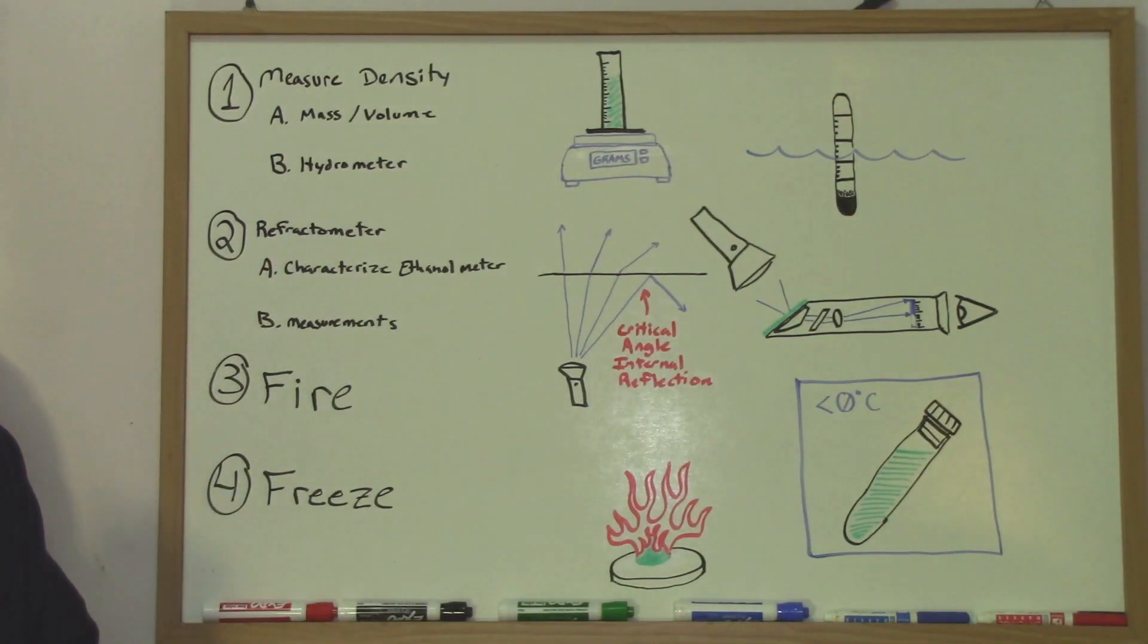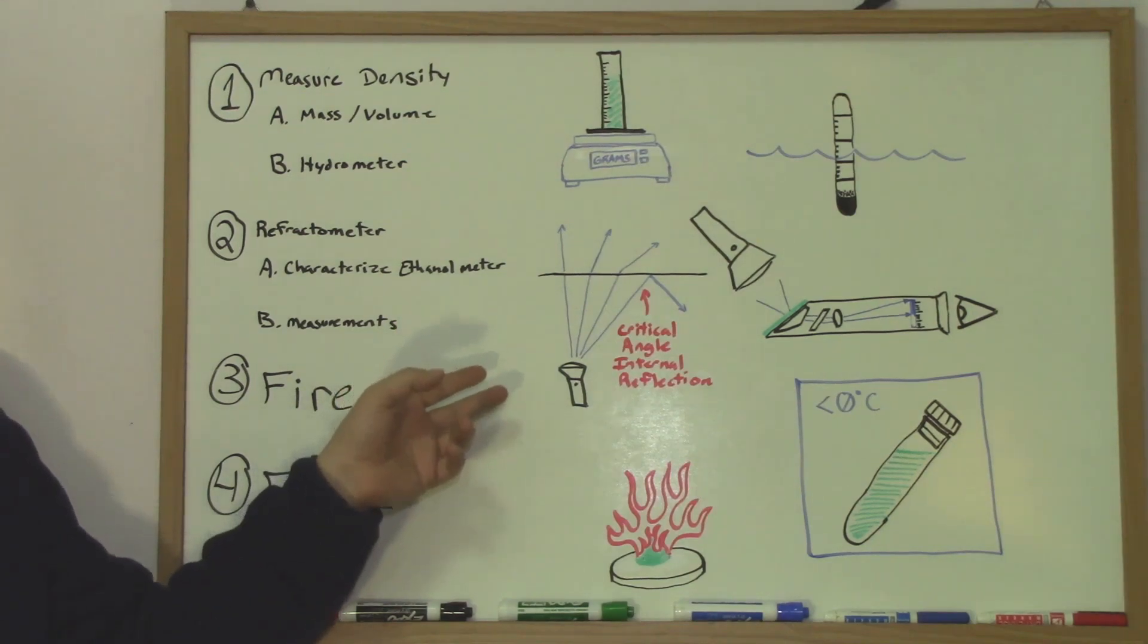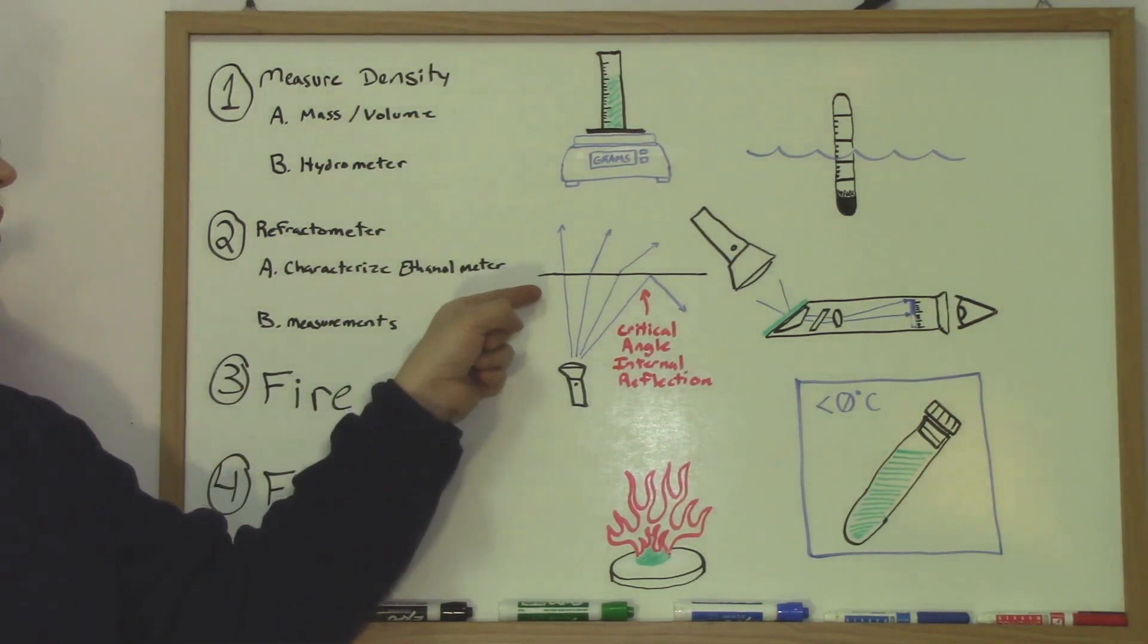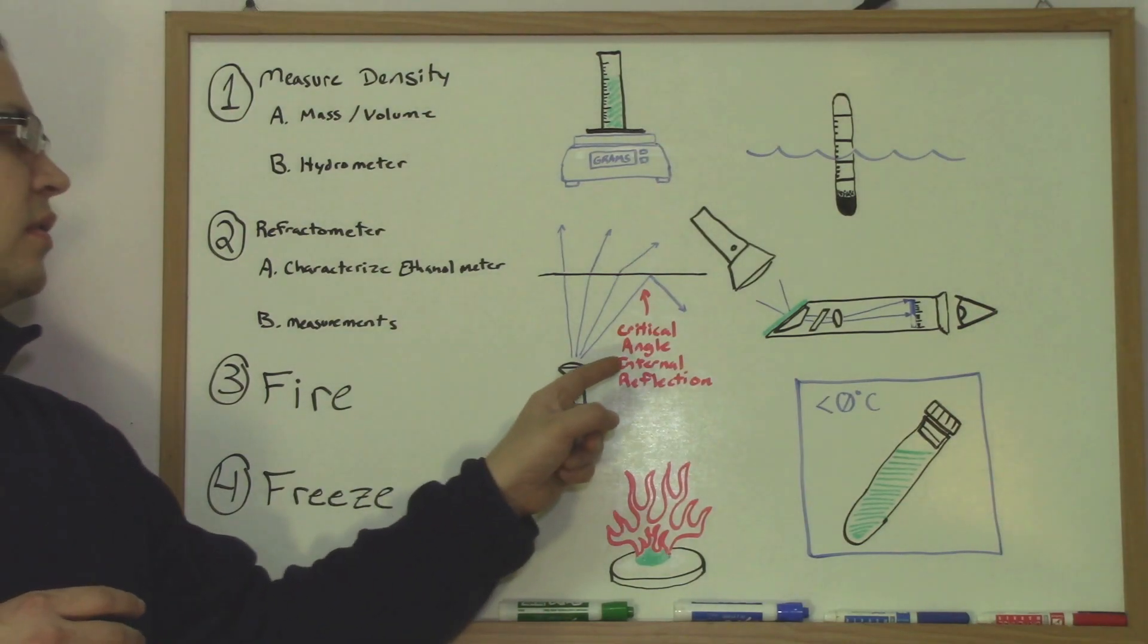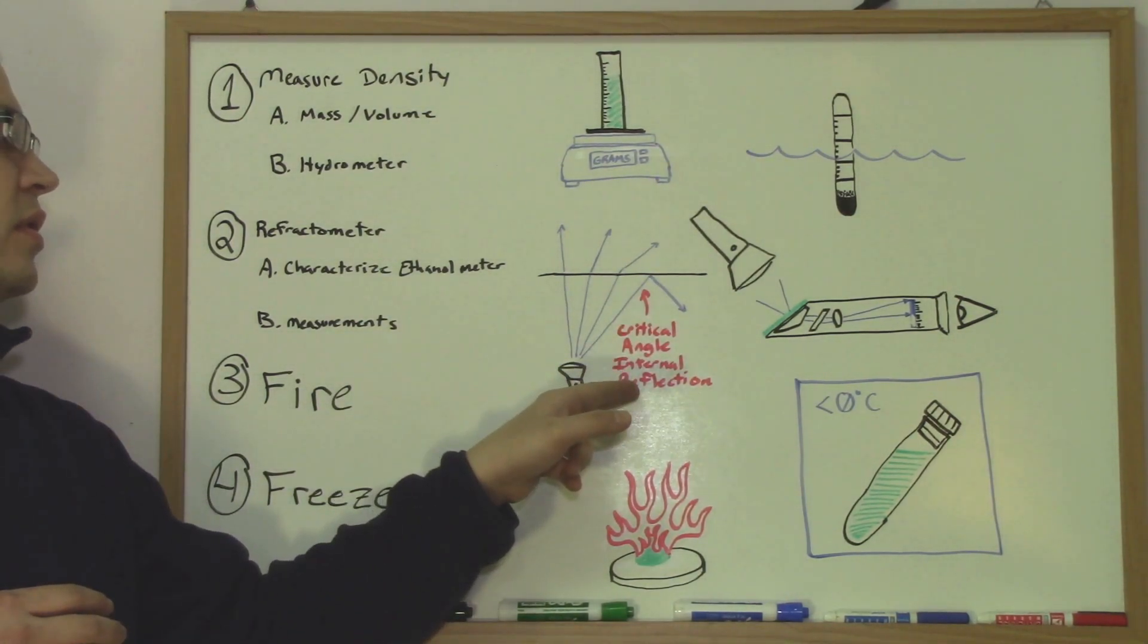The way that a refractometer works is it uses this concept where light changes direction at an interface between two different mediums. Two different mediums could be a solid and a gas or a liquid and a gas. It's using this critical angle where internal reflection starts to happen.